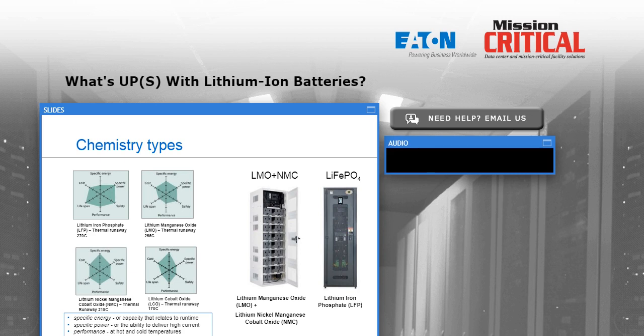But the combination of these two chemistries gives us better performance than either chemistry by itself. If you look at these two charts, specific energy is quite a bit better than the other one we just looked at, which means longer backup times. Safety is good, but not quite as good as lithium iron phosphate. Lifespan is good, cost is reasonable as well. So we do choose different lithium chemistries based on the application the customer tells us they need.